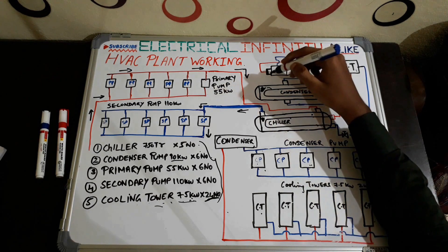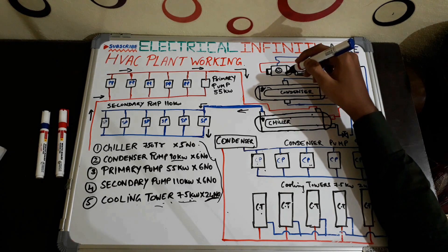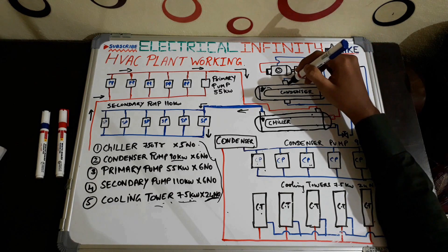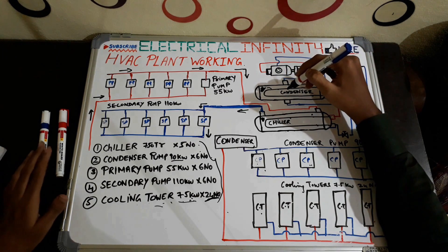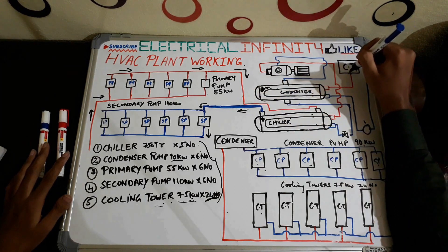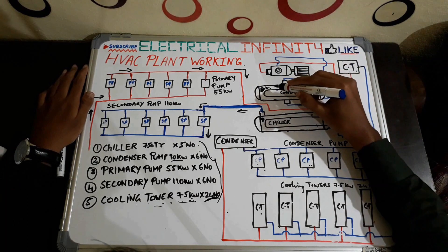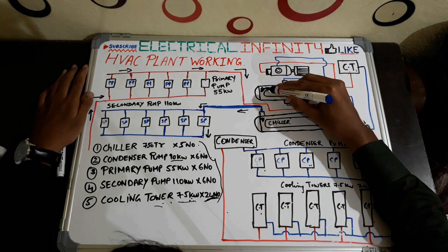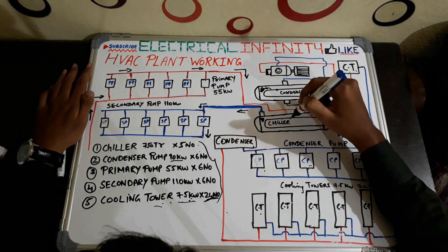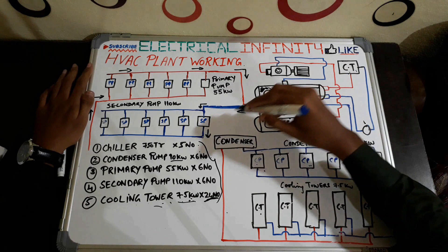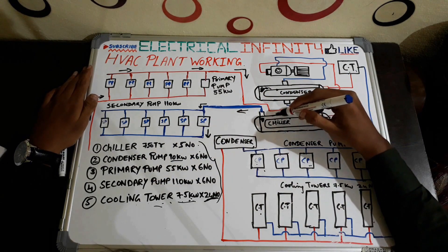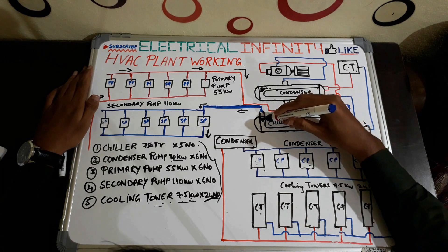The compressor compresses the high-temperature refrigerant and sends it to the condenser for cooling, where heat exchange takes place between the refrigerant in the shell type and the cooling water in the tube type. In the chiller, the refrigerant is in the tube type and the building cooling water is in the shell type — so heat exchange in the chiller takes place between the refrigerant in the tube type and the water in the shell type.